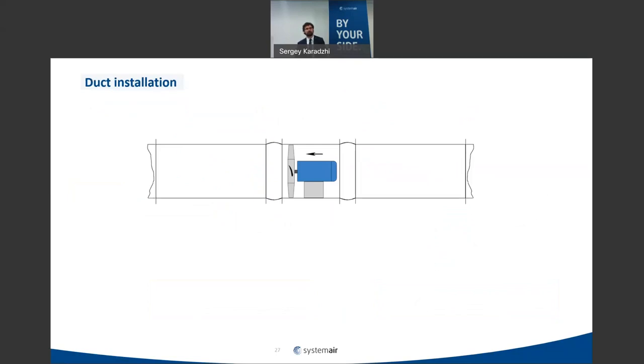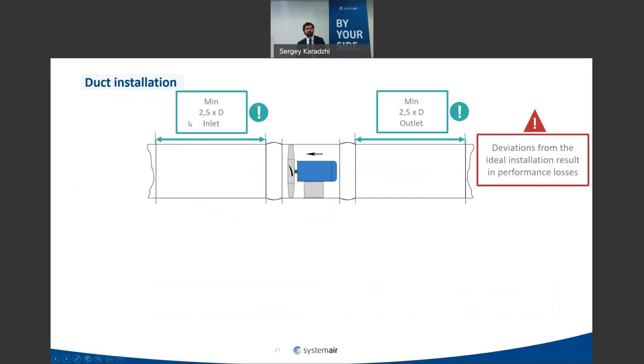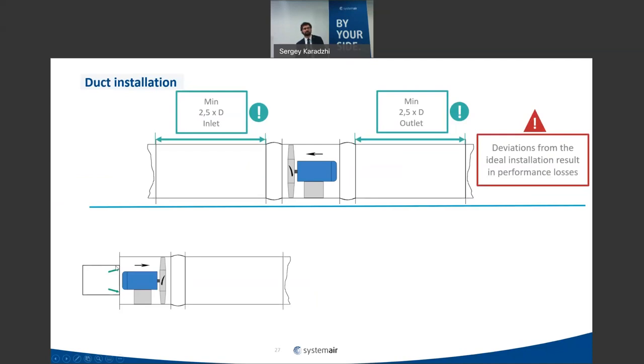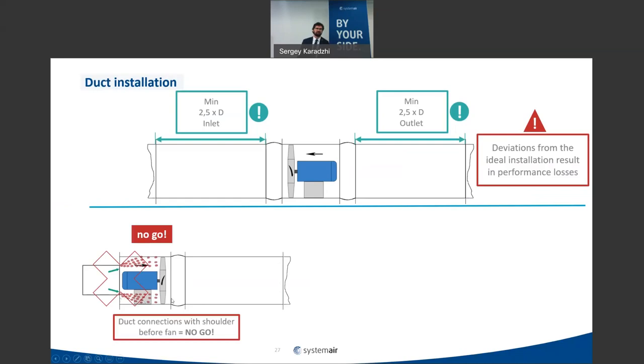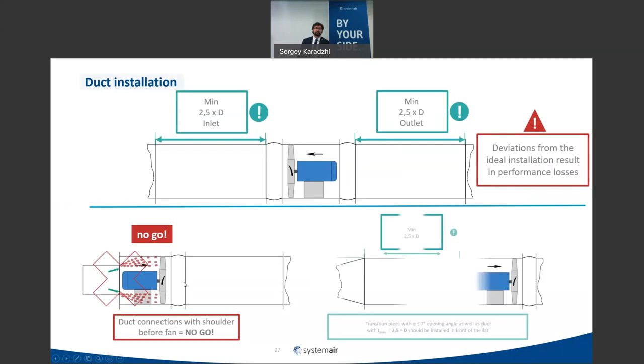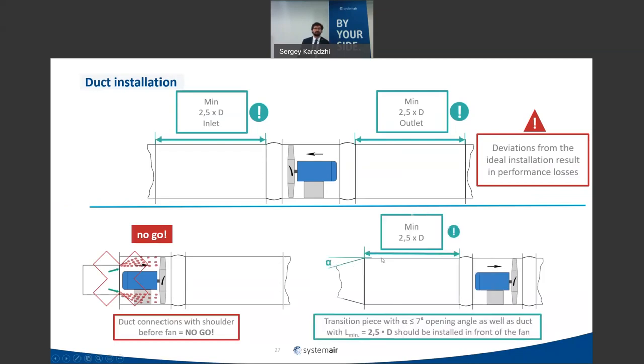For a fan with duct on both inlet and outlet, use flexible connections and think about minimum duct lengths. It's always better to have about 2.5 diameters of straight duct on both inlet and outlet to prevent influence from other duct components on the fan aerodynamics. A sudden increase in diameter is very bad — it creates flow separation entering the fan. Better to use a diffuser followed by a 2.5D straight duct section.